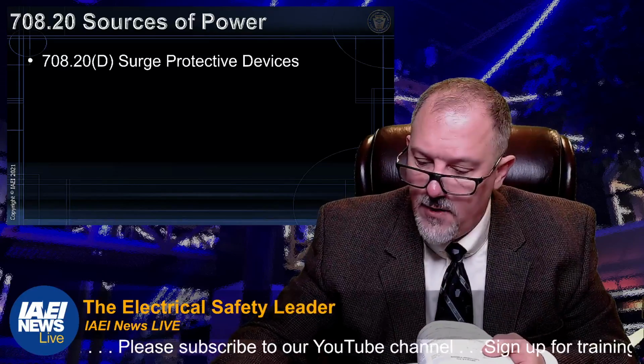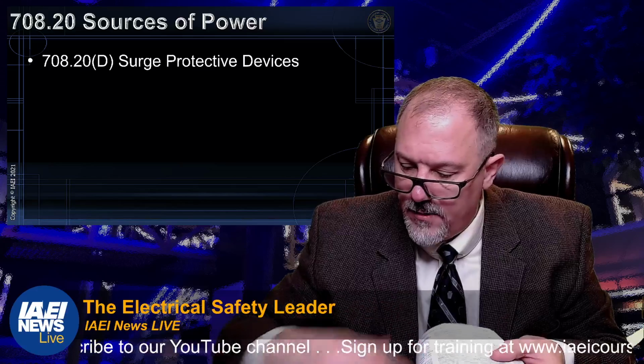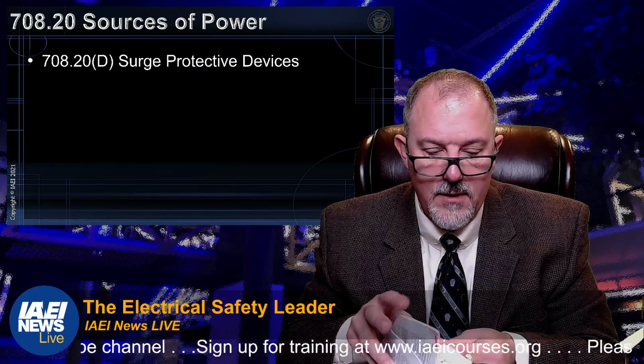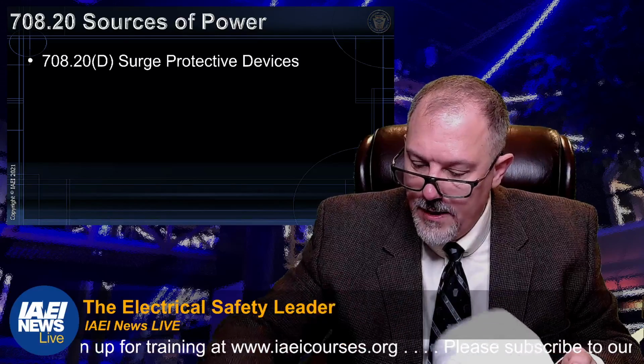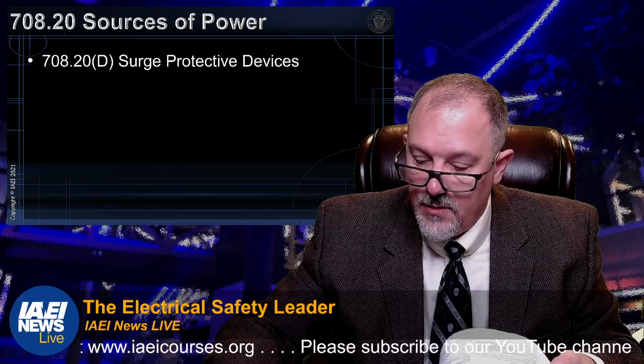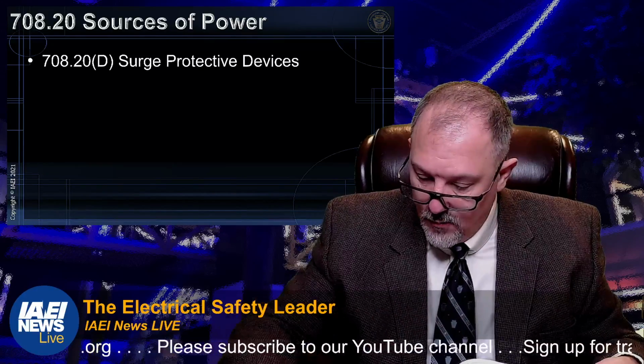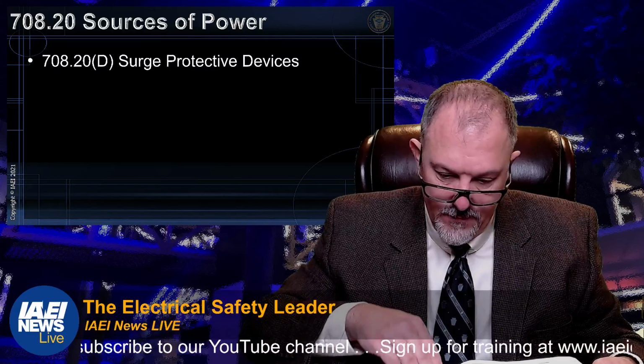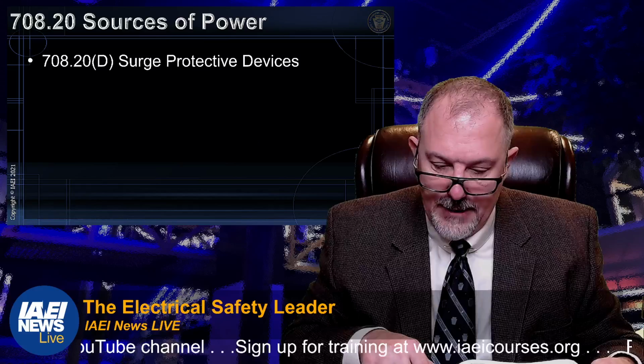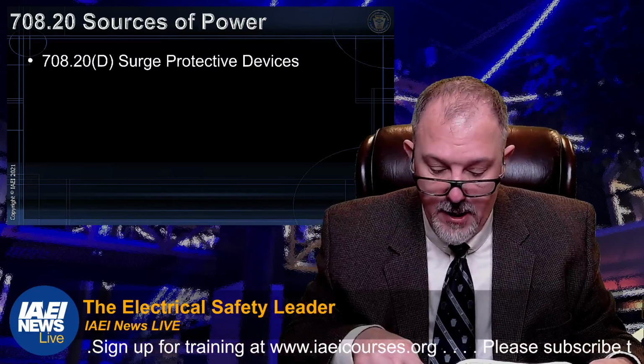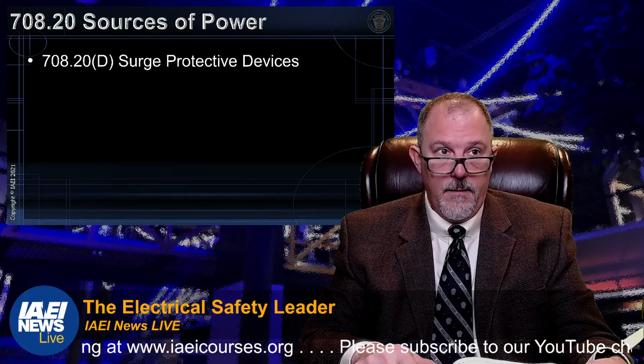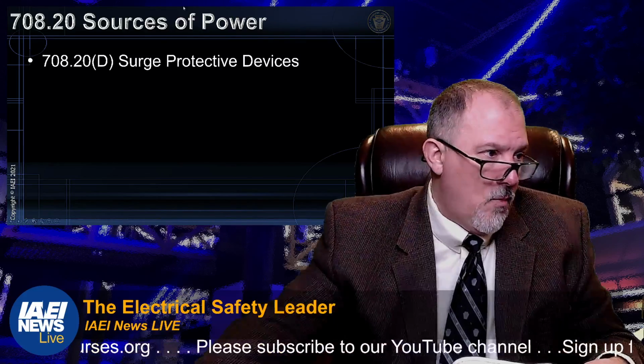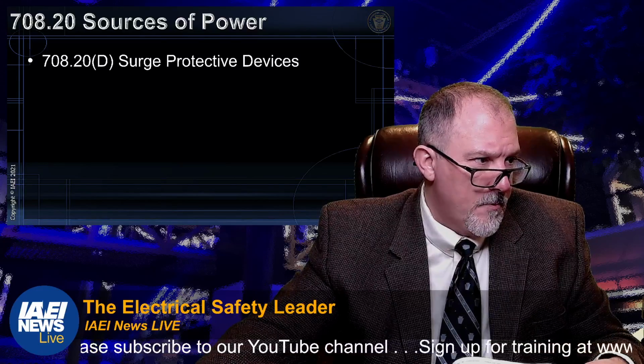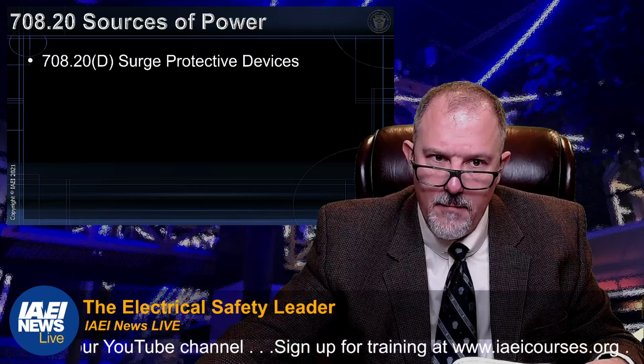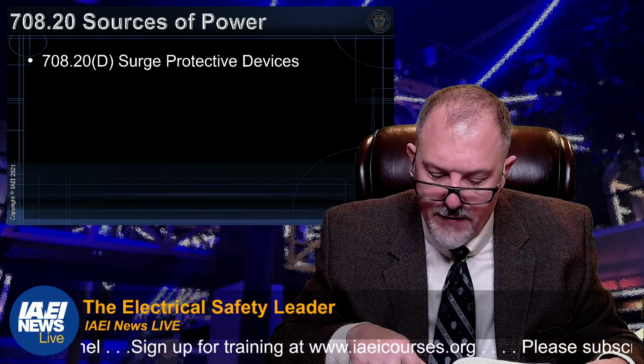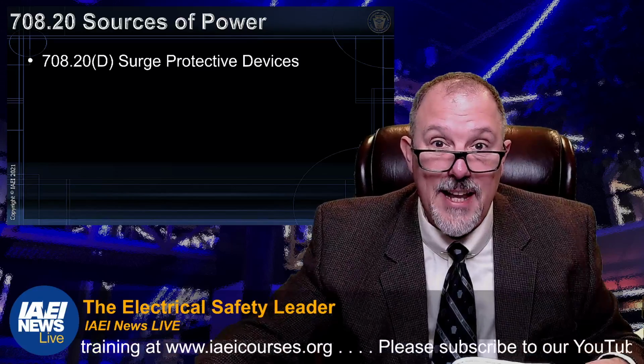708.20. Let's just take a look at 708.20. We're bouncing around, Tom. 708, 701, 702, 705, 706. Jiminy Crickets. 708.20 is titled Sources of Power, and D. Now remember, 708 is your critical operations power systems. Now this went in, trying to remember when, I think it was the 2011 code. But what it says is surge protective devices shall be provided at all facility distribution voltage levels.